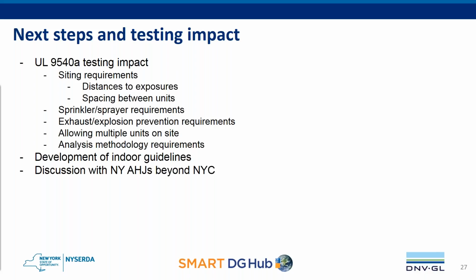That data will help them to get information on the heat release rates, which would allow a professional engineer to design a suppression system according to the heat release rates of that particular system. It will also help to figure out the flammable electrolyte release rate, and they will help to design an exhaust system to remove the flammable gases that are generated during a thermal runaway event. It will remove it so we'll never get above 25% of the LEL. It will also give some heat release rates for separation distances.